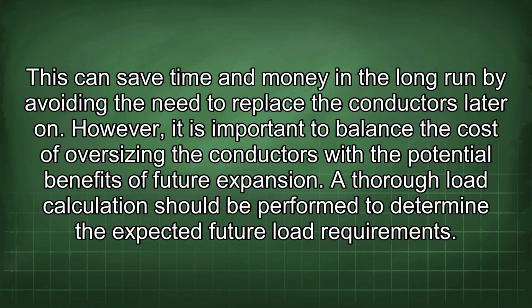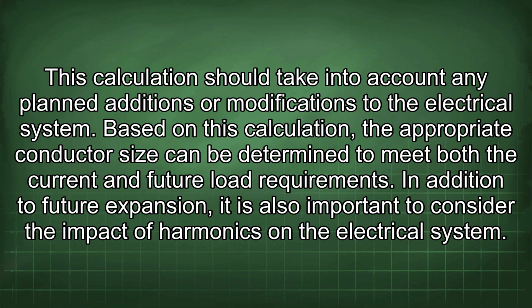However, it is important to balance the cost of oversizing the conductors with the potential benefits of future expansion. A thorough load calculation should be performed to determine the expected future load requirements. This calculation should take into account any planned additions or modifications to the electrical system. Based on this calculation, the appropriate conductor size can be determined to meet both the current and future load requirements.